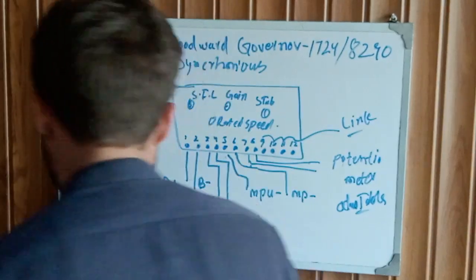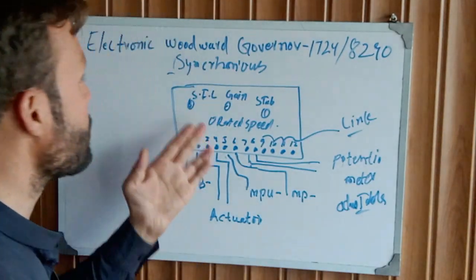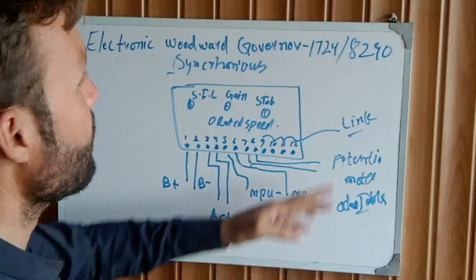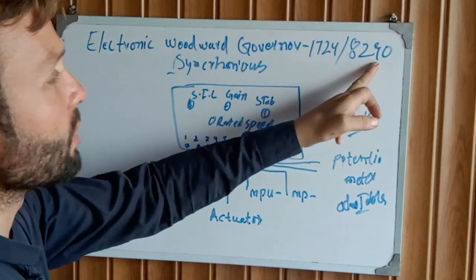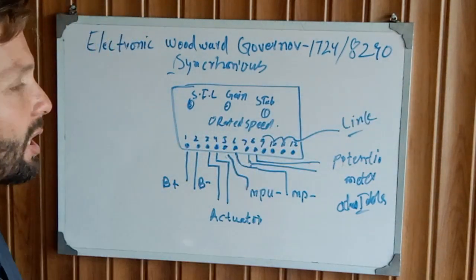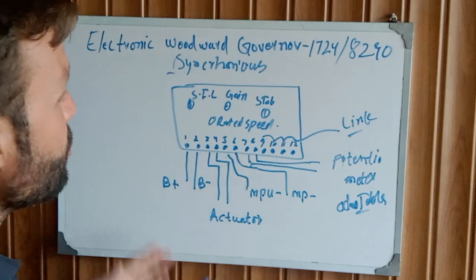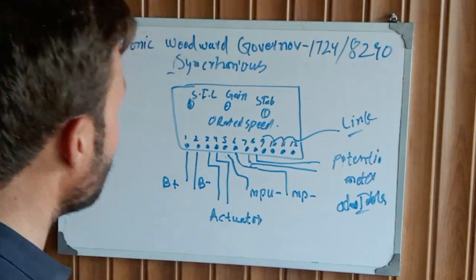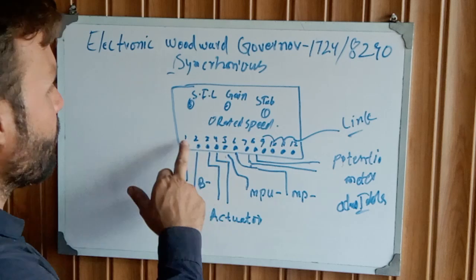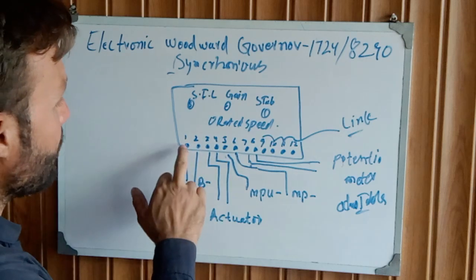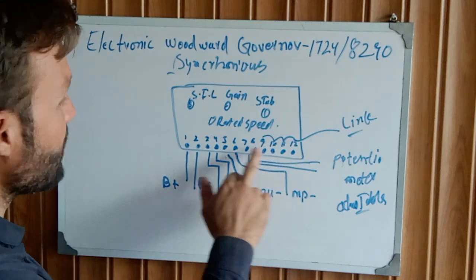Let's get started. This is the electronic fuel governor model parts number 8290. This is the governor and this is the diagram. Let me explain how to debug and install this governor. This governor has on the bottom side 12 terminals - you can see here 1 to 12.